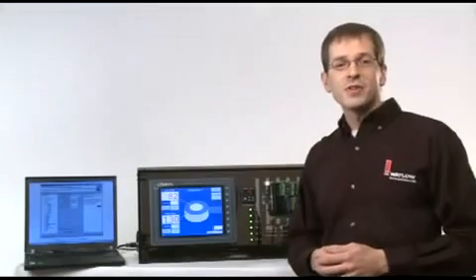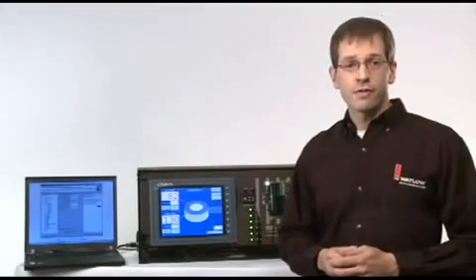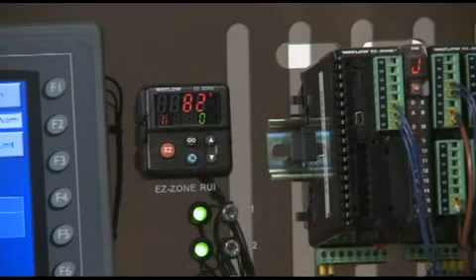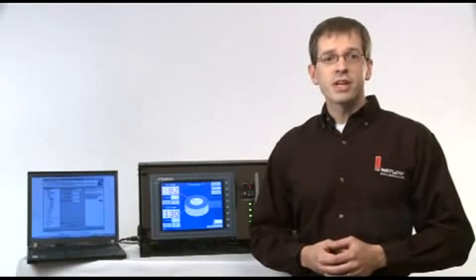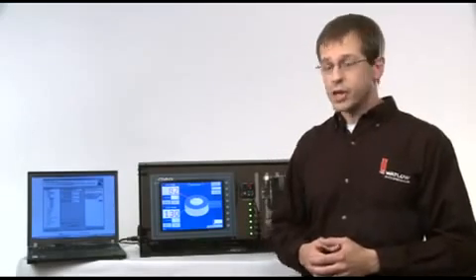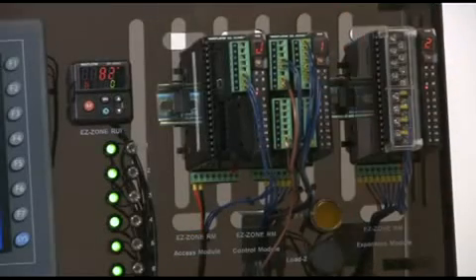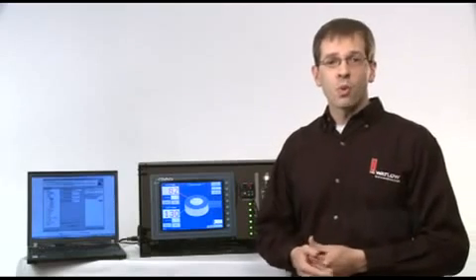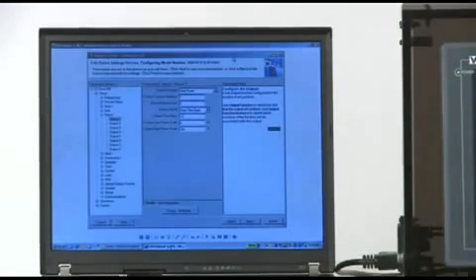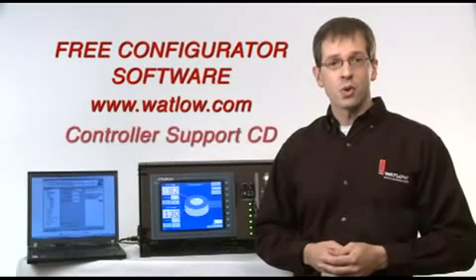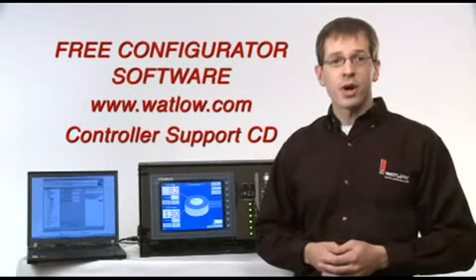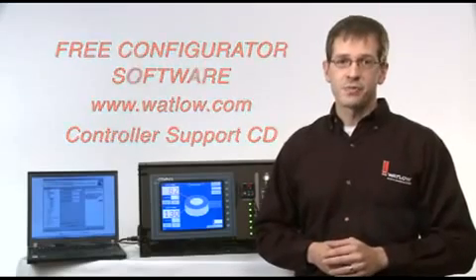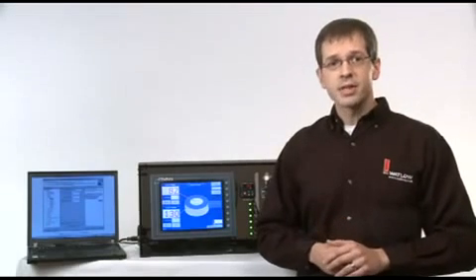A simple way to operate the EZ-ZONE RM is utilizing the Remote User Interface, or the RUI. The RUI gives you a full display so you can set the parameters of the EZ-ZONE RM. All you have to do is connect it to the standard bus and it automatically communicates with the control module with no configuration needed. Just like the other EZ-ZONE products, you can utilize the Watlow Configurator software, available free as a download at watlow.com or on your controller support CD. This configurator software allows you to easily interface with the device. For more sophisticated interface, you can use an HMI, communicating with the EZ-ZONE RM by one of the industrial protocols like the Modbus RTU.